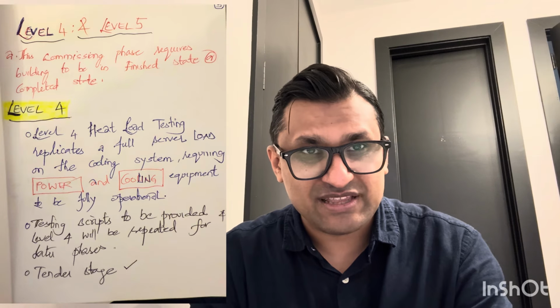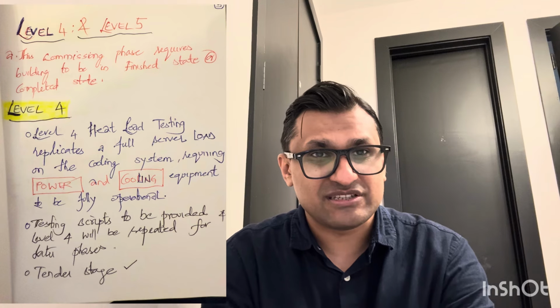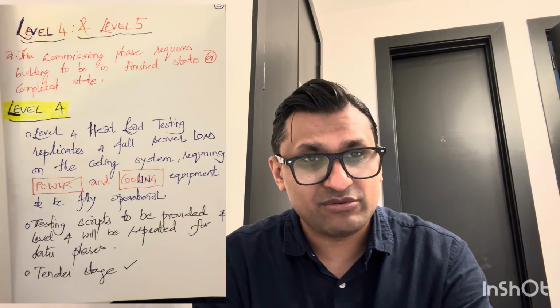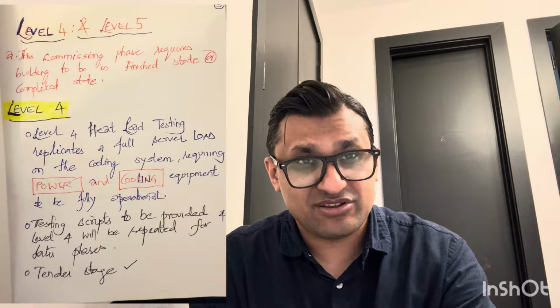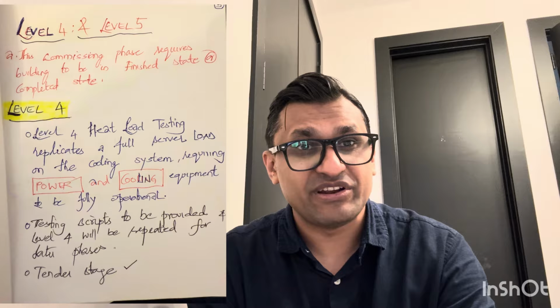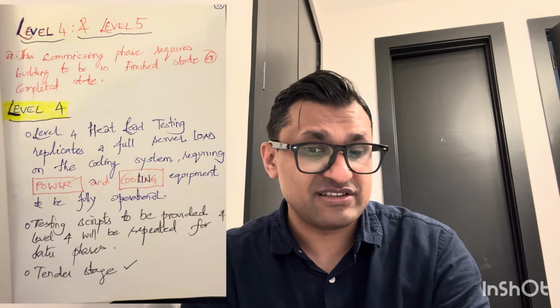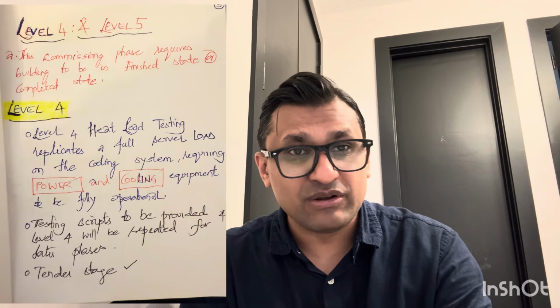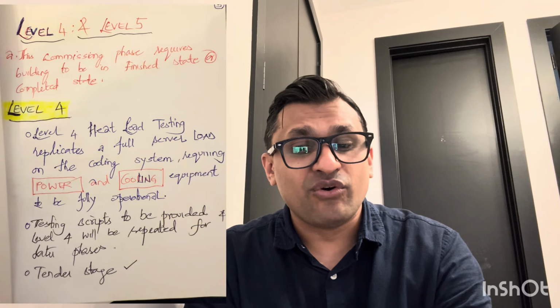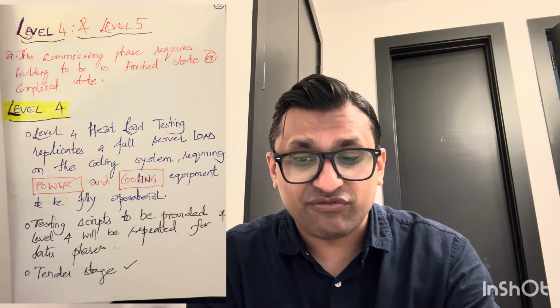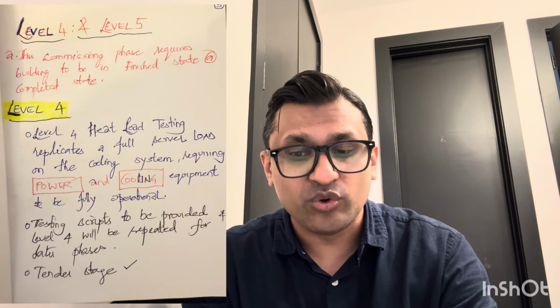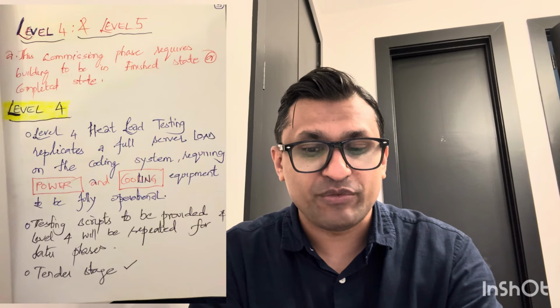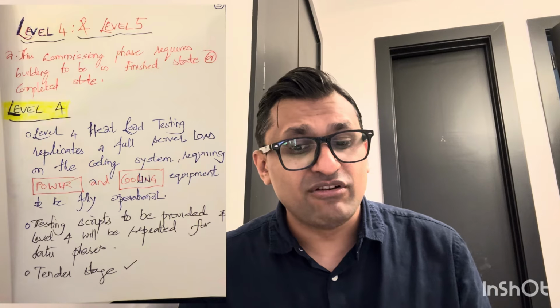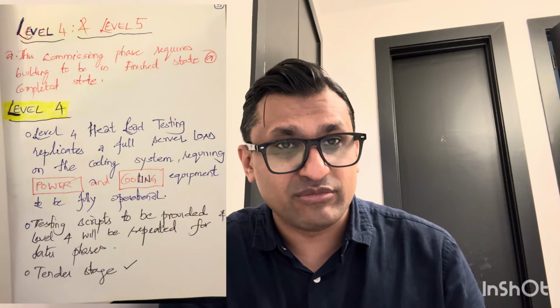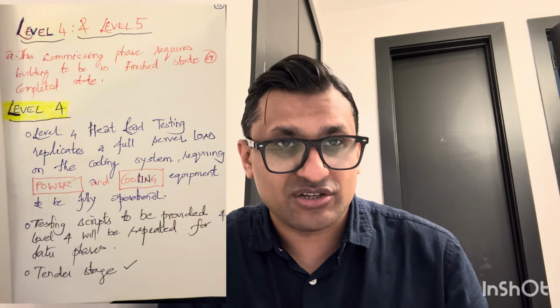The groundwork is laid. The testing and commissioning is done by the HVAC, plumbing people, and the utilities team, and the general contractors are all out of the building. They've completed the job. Level 4 is that commissioning phase. It requires the building to be finished. Level 4 heat load testing replicates a full server load on the cooling system, requiring power and cooling equipment to be fully operational. Level 4, basically you are simulating and testing a full load condition on the building.